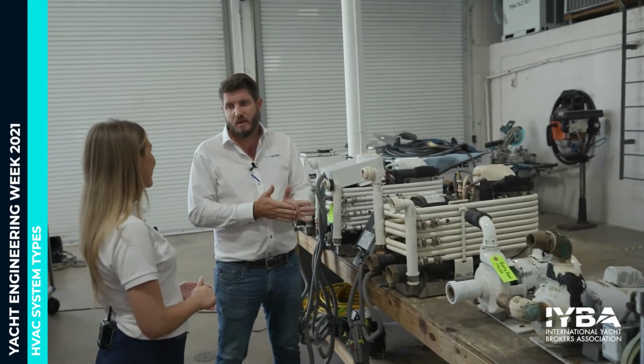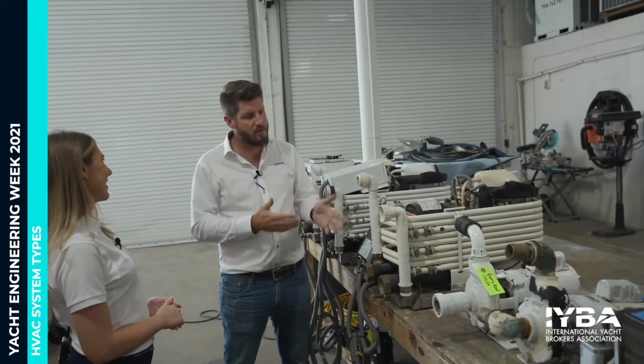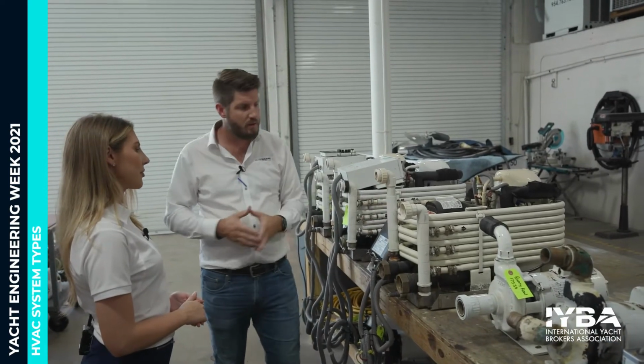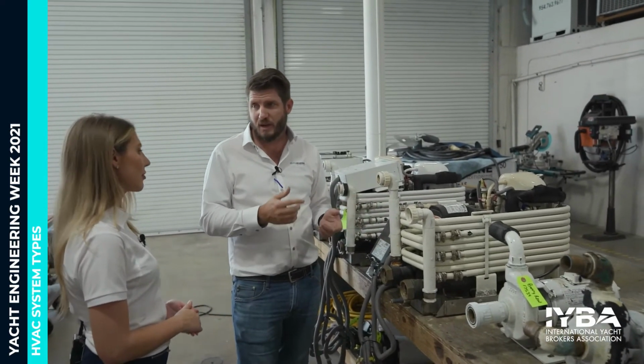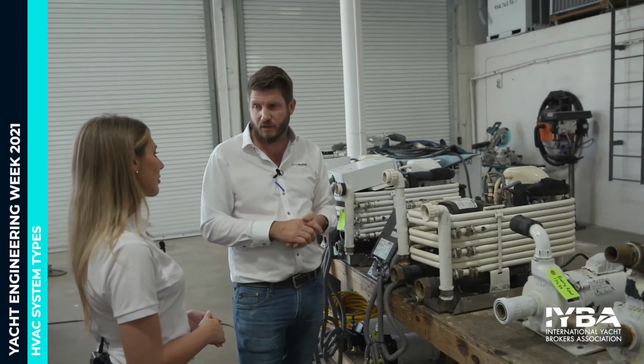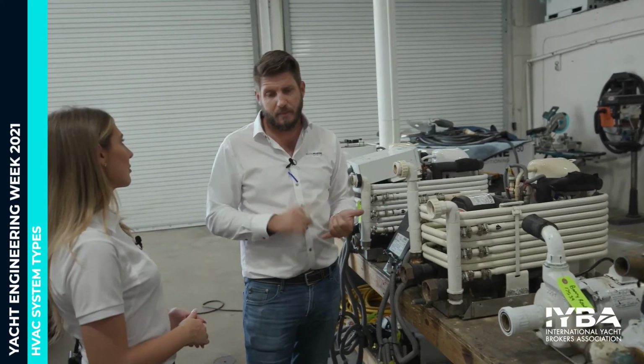And what if there is outside air? Then we have problems. Let's say the condenser coil ruptures and seawater gets in, then we have to totally flush out the whole refrigerant circuit. We can't have any air, moisture, non-condensables in that system. It has to be purely refrigerant.